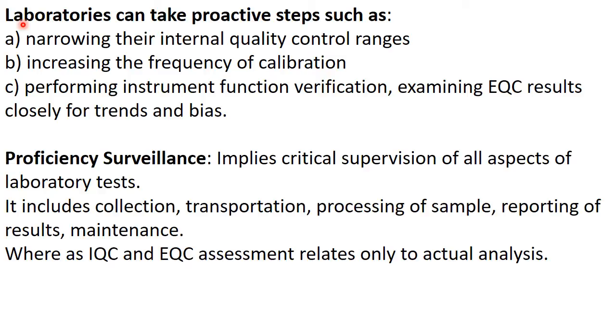Next, laboratories can take proactive steps. Proactive steps means what measures are taken after performing the quality control: narrowing their internal quality control ranges, increasing the frequency of calibration, performing instrument function verification, examining external quality control results closely for trends and bias. These measures can be taken.